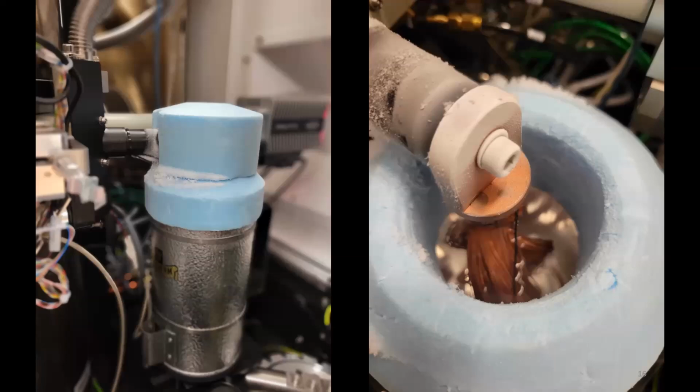So when you put your sample in, because we're at such a high vacuum, all of the stuff that's on your sample, things that are just gathered from the air, moisture, all that's going to start evaporating. And if it were to evaporate and not have anywhere to go, it would end up in the IGP, the gettering pump. And we don't want to do that because there's only so much gettering the gettering pump can do before it has to be recycled. It has to go through a heating and all kinds of stuff. And you don't want to do that very often.